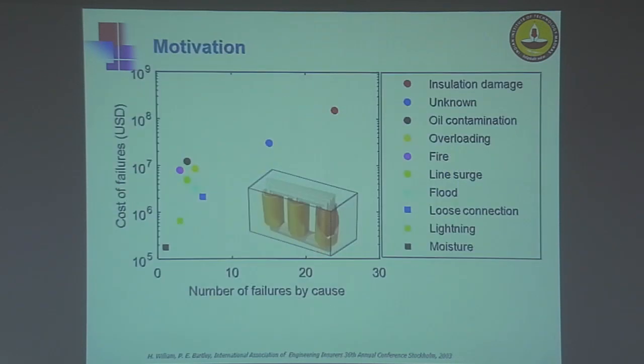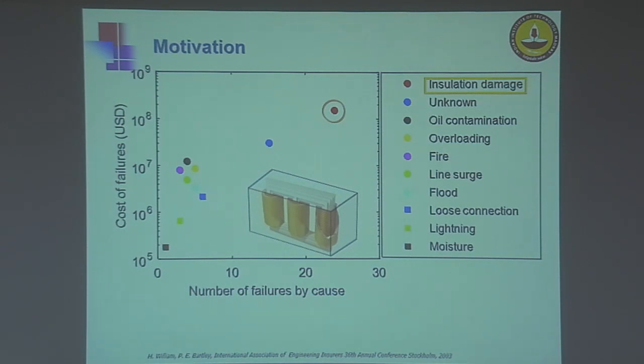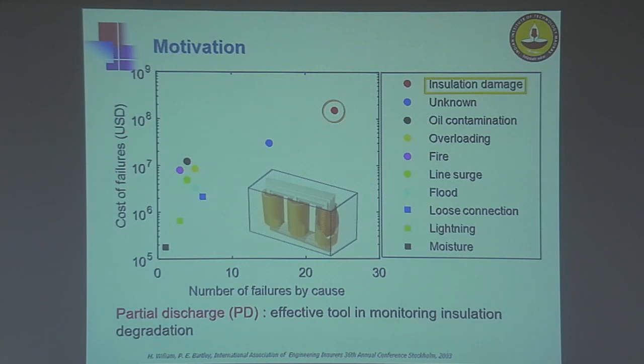An interesting study conducted a decade ago on the analysis of failures of power transformers revealed that the most frequent and costliest reason for transformer failure is damage to the insulation. Just like every one of us, the transformer also experiences a lot of stress during its working, and the insulation weakens as a result of continuously accumulated electrical, thermal, and mechanical stresses over long years of operation. It has been shown that these weak spots in insulation are prone to what are known as partial discharges, and these discharges act as precursors to transformer failure. Monitoring the level of partial discharge can therefore be an effective tool for ensuring the health of the insulation.